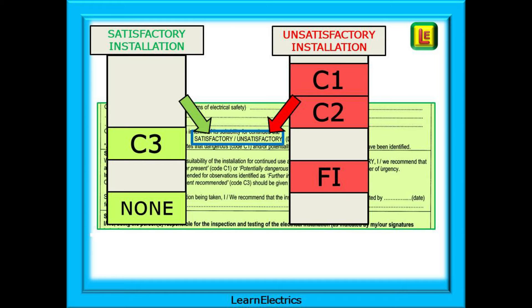The outcome of an electrical installation condition report can be either satisfactory or unsatisfactory. If the observation codes are only C3, or there are no observations, then the installation is satisfactory for continued use. But if there are any C1, C2 or FI observations then the condition of the installation is automatically deemed unsatisfactory, meaning that remedial action is required. There is no minimum number of C1s, C2s or FIs — just one will make it unsatisfactory.